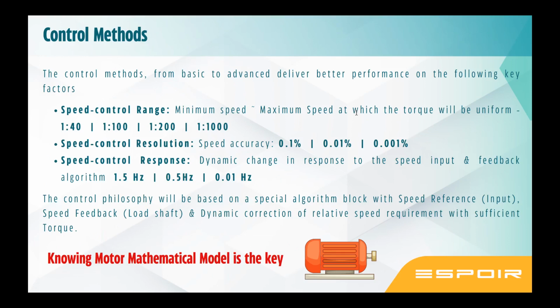Now, in a V by F method, minimum to maximum speed is a 1:40 ratio. Means if your rated RPM is 1440, you just divide it by 40. So what is coming, say 35 RPM? 35 RPM is the minimum RPM you can achieve. Below that, you cannot achieve. Now, not just achieving the speed, also achieving the required 100% torque at that RPM, which is the aspect. Getting sufficient torque at 35 RPM is a very difficult task to achieve. Now, if you want to reduce and get a better performance much lower than 35, then you have to tune the system.